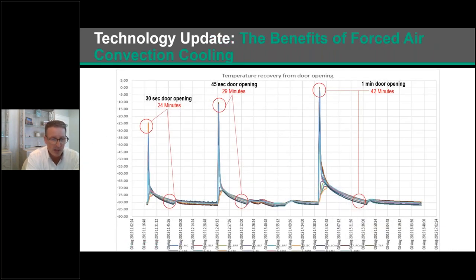So on this slide, we're talking about temperature door recovery. On the previous slide, we mentioned the cold wall freezer taking 3 to 5 hours. But as you can see from the current slide, the temperature recovery from a FARRAR ULC forced air convection system offers a much faster recovery. As you can see, from a 30-second door opening, it was 24 minutes. And in the middle of the graph, from a 45-second door opening, it was 29 minutes. And from a 1-minute door opening, this was 42 minutes. And again, this is the same for either the 190 cubic foot chamber or the 311 cubic foot chamber, empty chamber and with the full inner door being open.